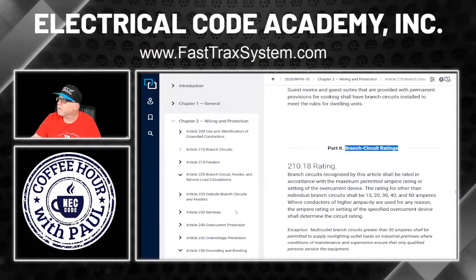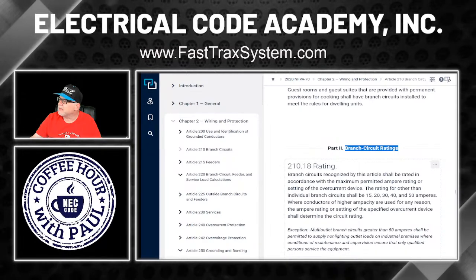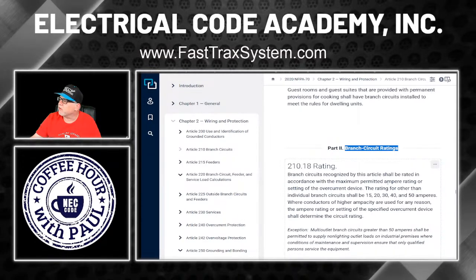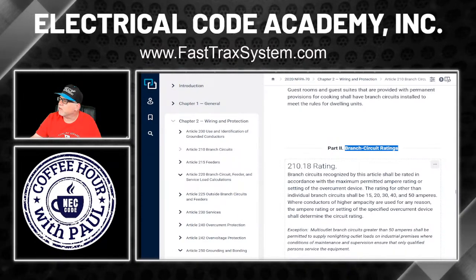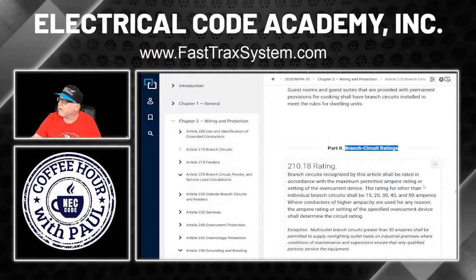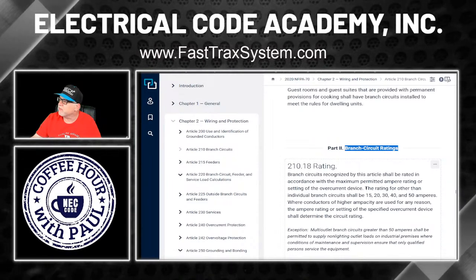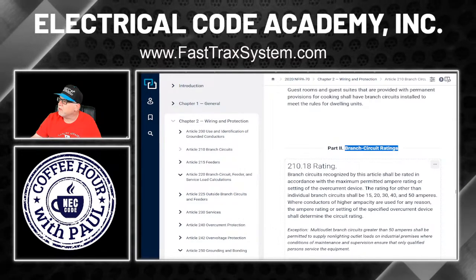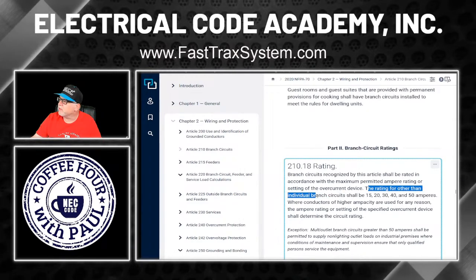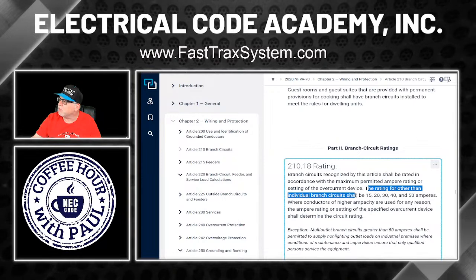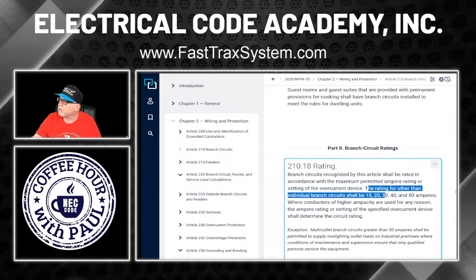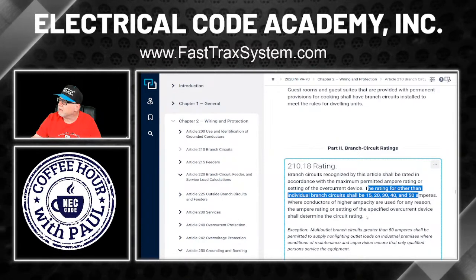Maximum rating. All right, so in .18, it says branch circuits recognized in the article shall have a rating in accordance with the maximum permitted ampere rating or setting of the overcurrent device. Okay, so the rating other than individual shall be 15, 20, 30, 40, and 50, that type of thing.